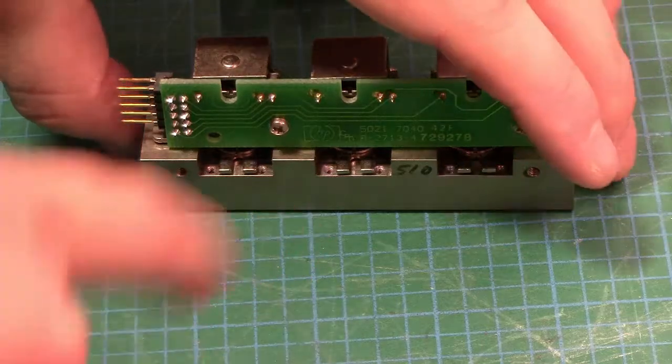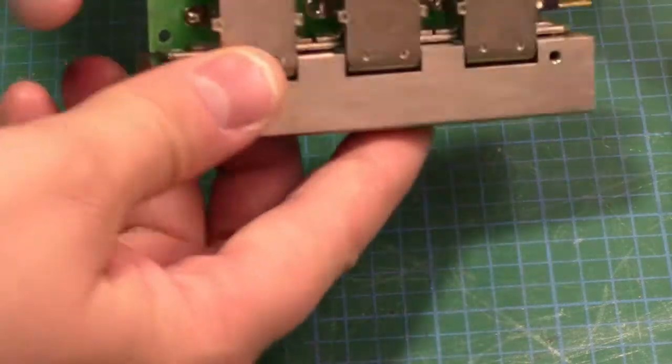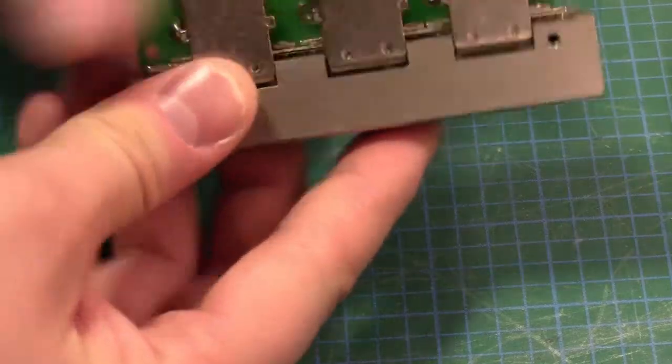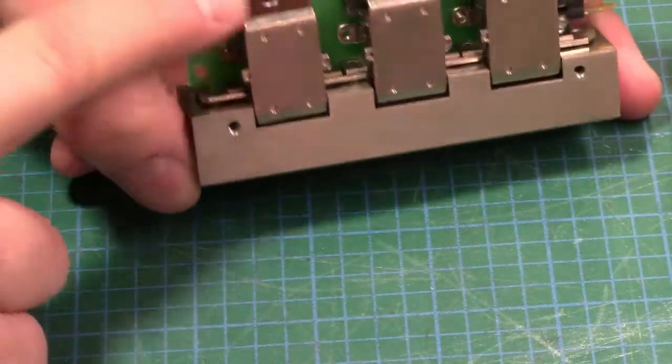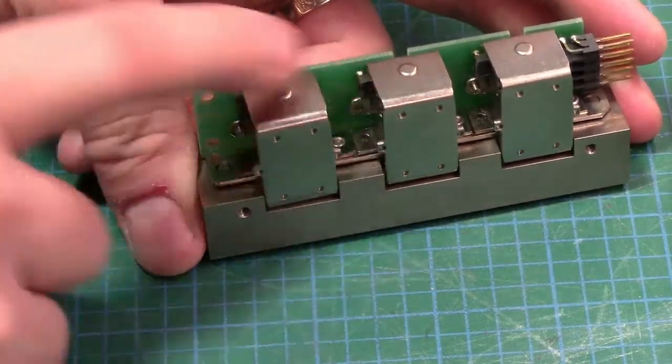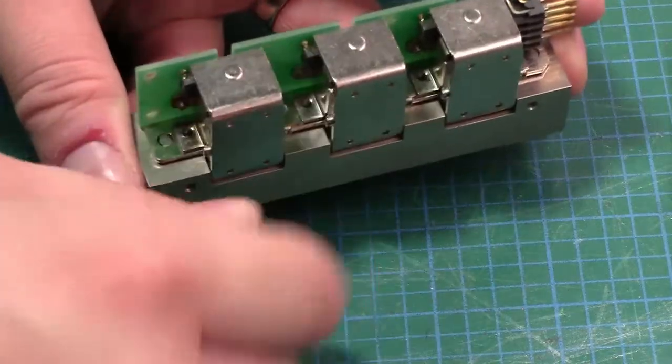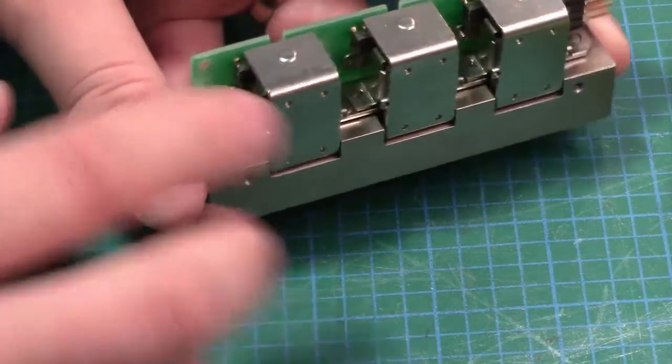After we remove all the screws and everything here, these two modules will come apart. Just be careful. There's a shield right here that can completely come out. It's held in by a set of magnets on each one of these relays, but just remember it can come out so it may reposition itself.